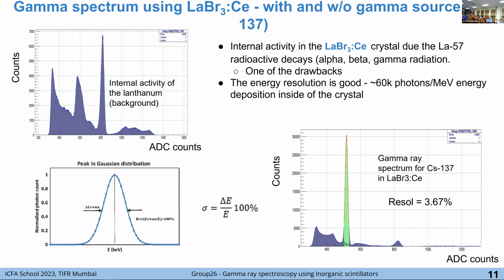In another top picture you can see the background for the lanthanum crystal without any gamma ray source. Here you can see the lanthanum alpha decay and gamma ray spectrum. So it has a background up to 2 MeV, which affected our results. If you put here the cesium-137 gamma ray source, we will see a sharp peak around 660 keV, and the resolution here is about 3-4%. Resolution can be defined with this formula: it's the ratio of the full width at half maximum to the energy, in terms of percent.